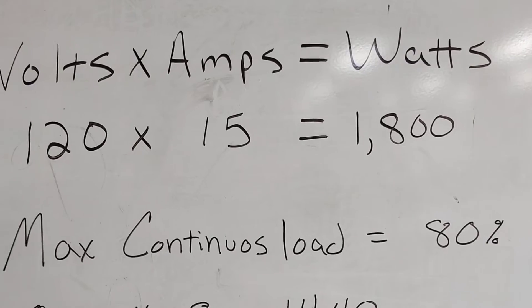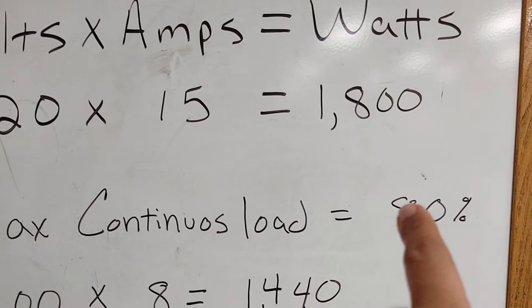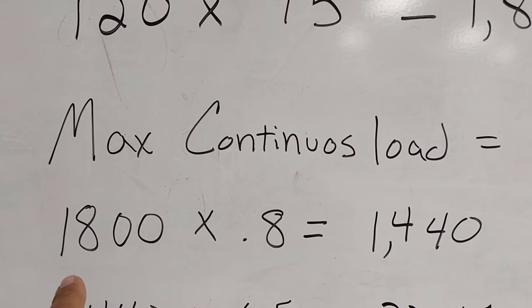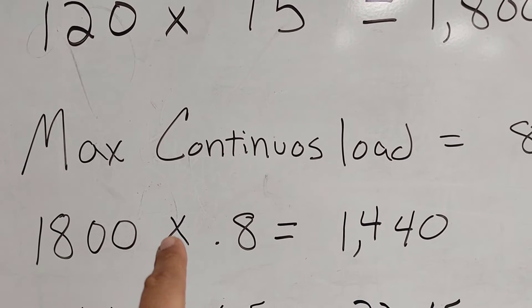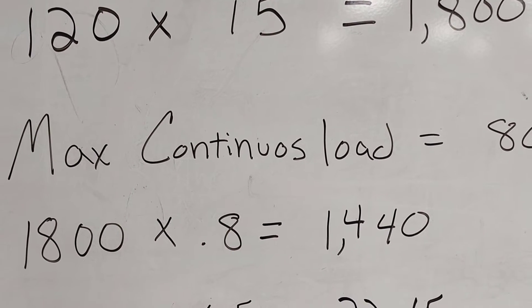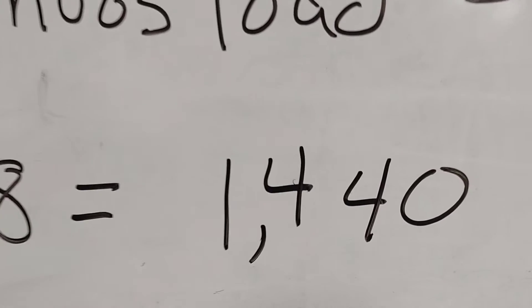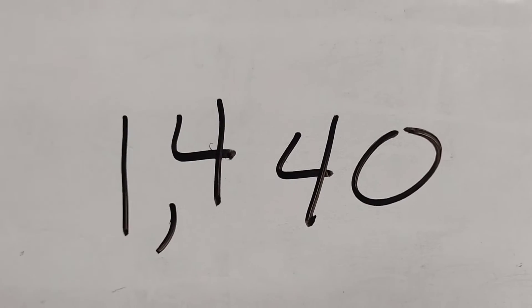Now we have our watts, but there is one rule we need to know: for continuous load, we can only be at 80%. With our maximum continuous load only being allowed to be 80%, we want to take our 1,800 watts and multiply that by 0.8, which gives us 1,440 watts. That's the number we're going to use to calculate how many lights we can put on that circuit.